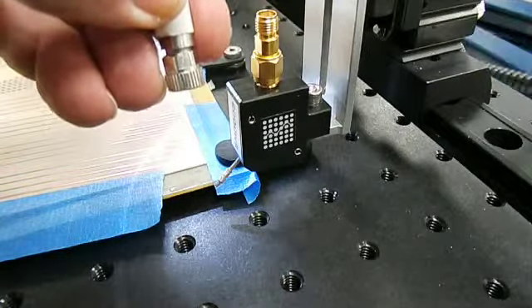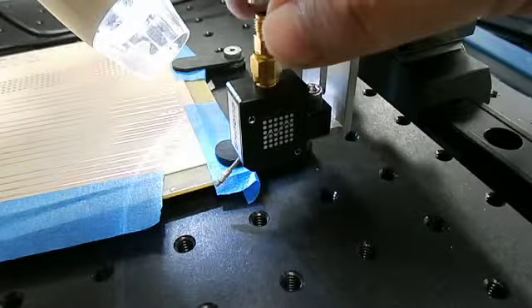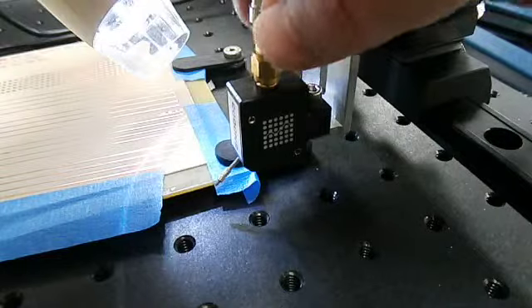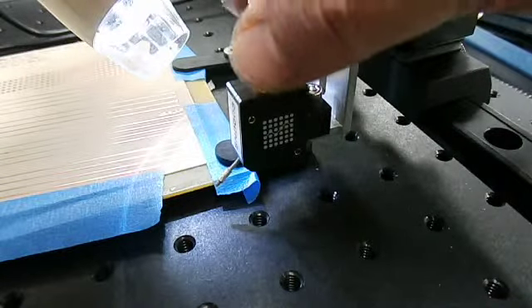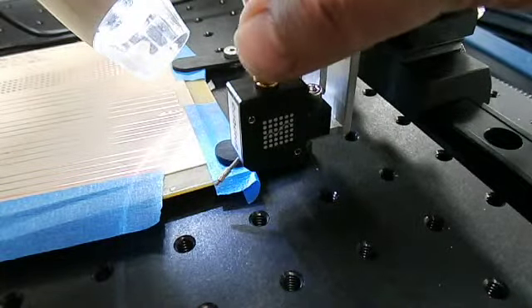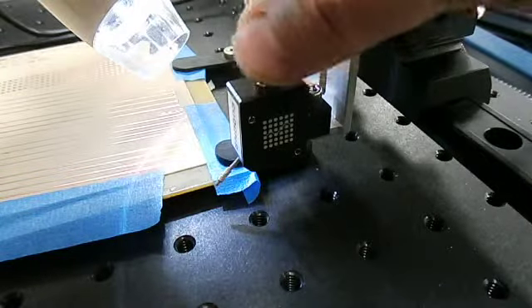With the FastProbe connected to the bracket, we're now going to connect the test port cable. The FP12 has an SMA cable connector for the top, but it will mate with SMA cables, 3.5 millimeter cables, or 2.92 millimeter cables, also known as K cables. You see that I'm actually touching the connector and the probe with my hand. I'm strapped in with my other wrist with an ESD protection strap to make sure that the probe is at the same potential as the instrument before making the connection.